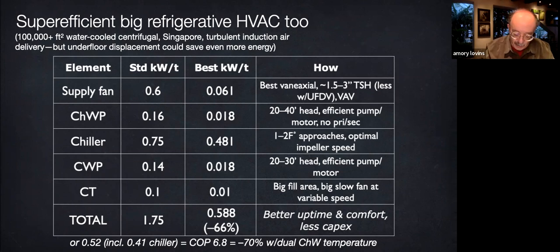Mr. Lee rigorously designs out duct and piping friction. So the supply fan has only about 1.5 to 3 inches water gauge of total static head. And you can do less, even an inch or less, with underfloor displacement ventilation. The chilled and the condenser water loops similarly have heads of only 20 odd feet.